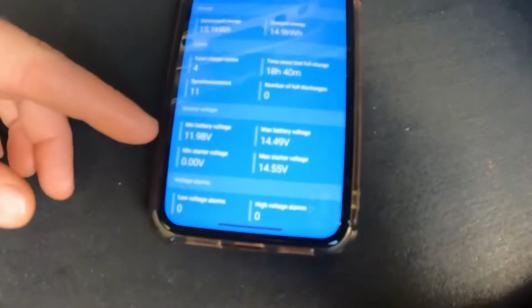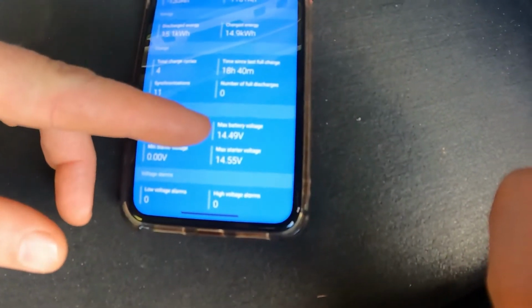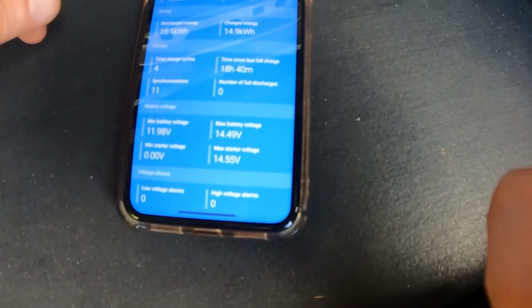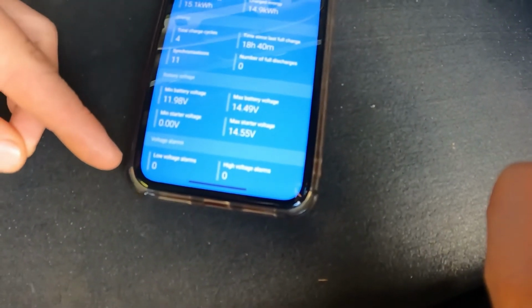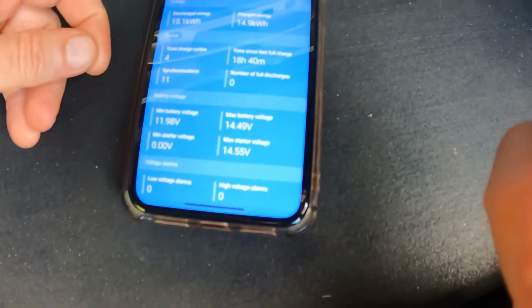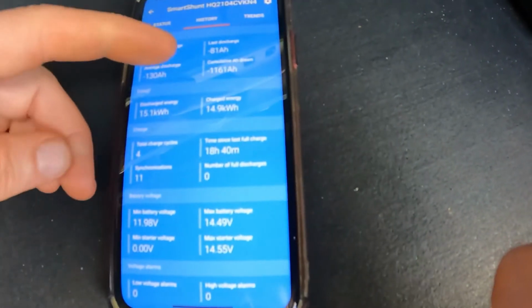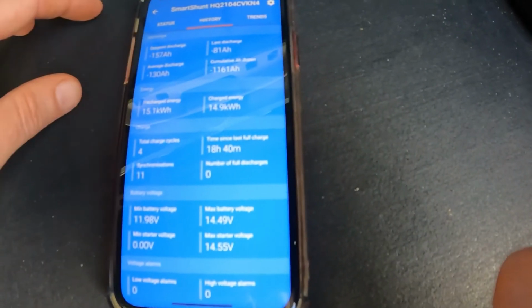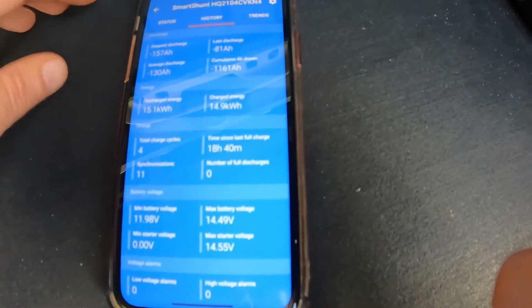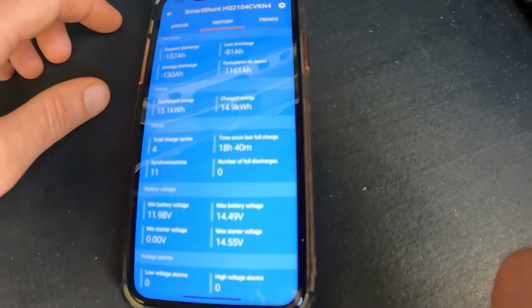We can also see minimum battery voltage, maximum battery voltage, max starter voltage. We've had no alarms for low voltage, and no alarms for high voltage, which is great. Cumulative amp drawn is 1161 amp hours, and last discharge we only used 81 amp hours.